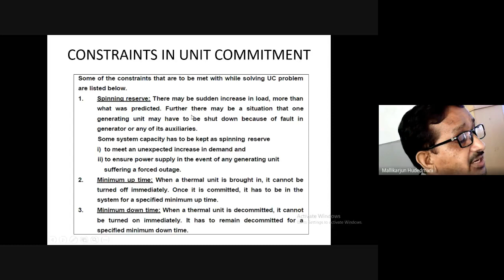As we were discussing, spinning reserve is ready-to-use energy already being generated at the plant while meeting the current load requirement. This is to absorb sudden changes in load. Suppose there is an increase in load, the system should cope without switching on any additional generator. Or, spinning reserve is useful when a generator suddenly decreases its output due to internal or external causes. That deficit megawatt from that generator is adjusted and covered by the remaining generators through proper tuning, so that the system immediately returns to normal mode. This is how, to meet balanced delivery, spinning reserve plays a vital role.